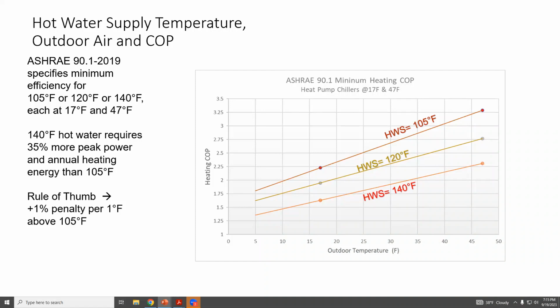Trane is developing for ultra cold climate ambient, but it's not currently on the market. The other trend is when you look at certain temperatures of hot water you're producing, as well as the ambient you're looking at, there are derates to your system. As you produce hotter water, and as you go to lower ambient, you're not going to get as many BTUs out of an air source product, and your equipment becomes less efficient.